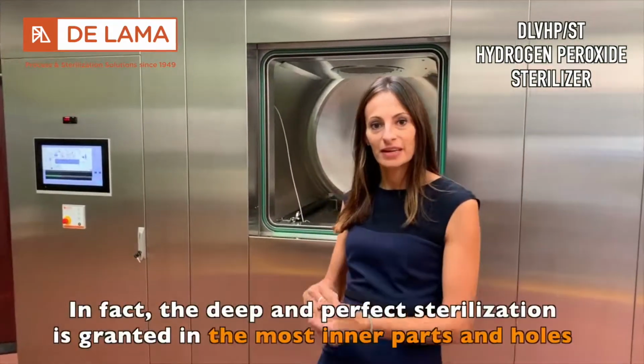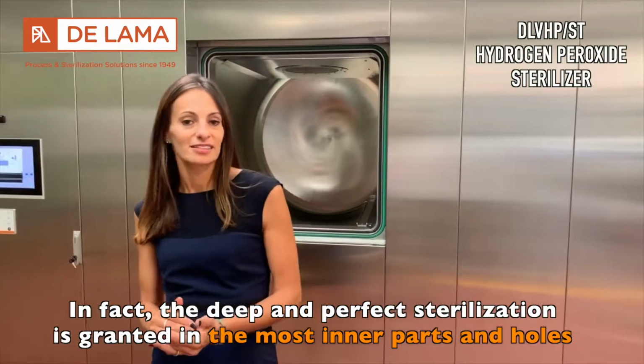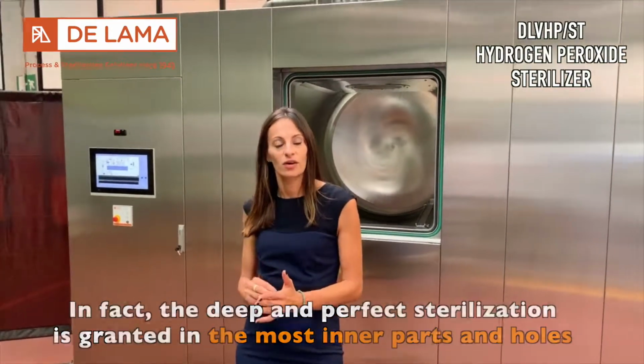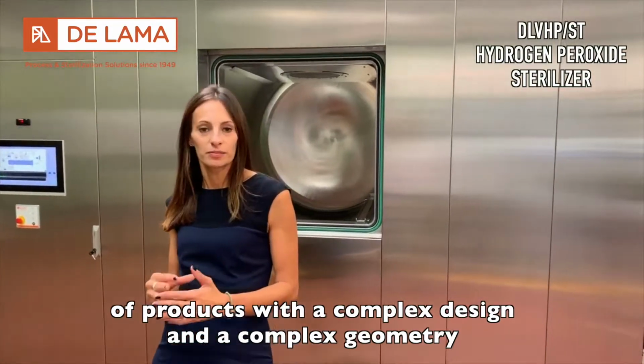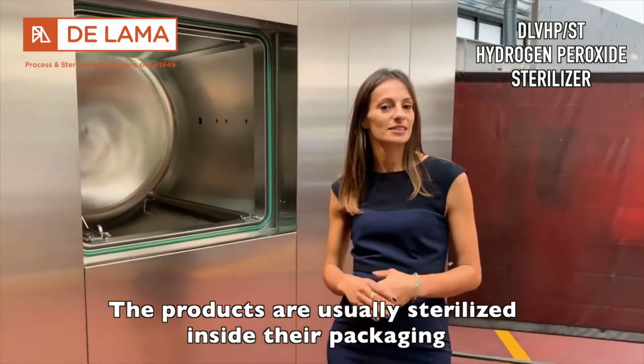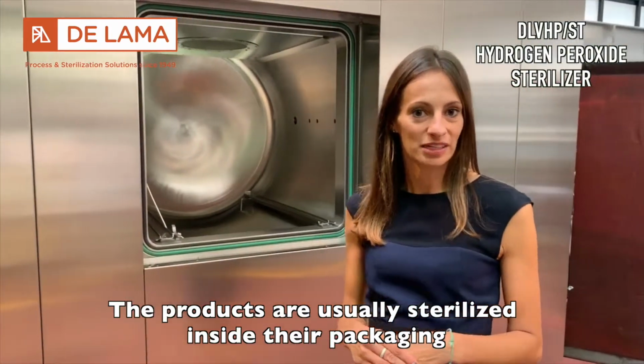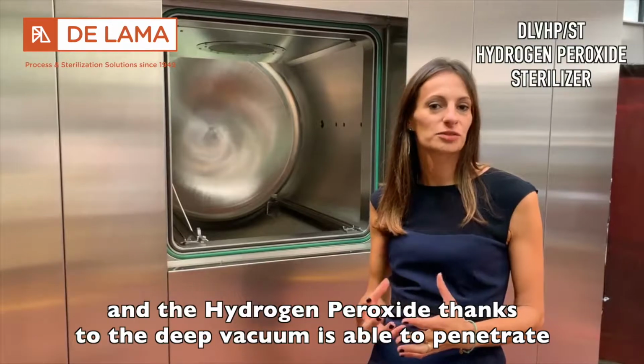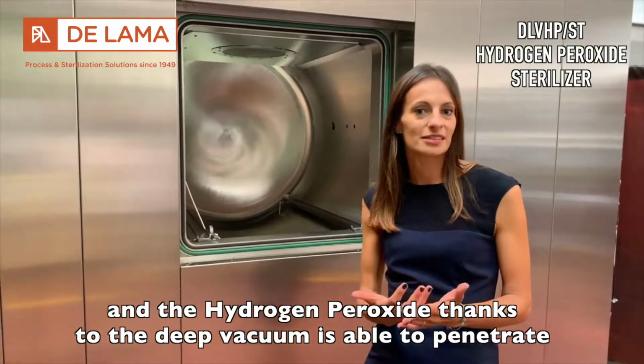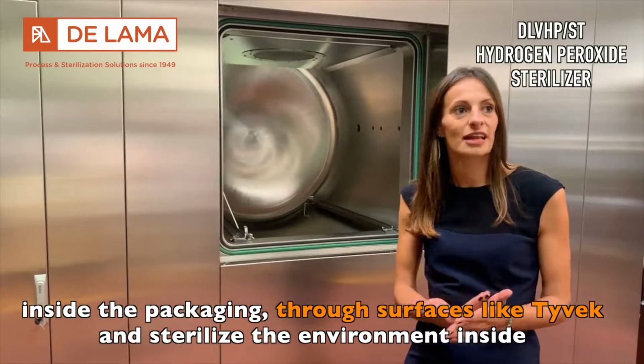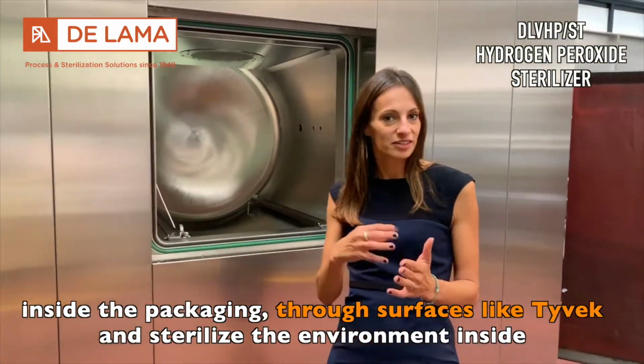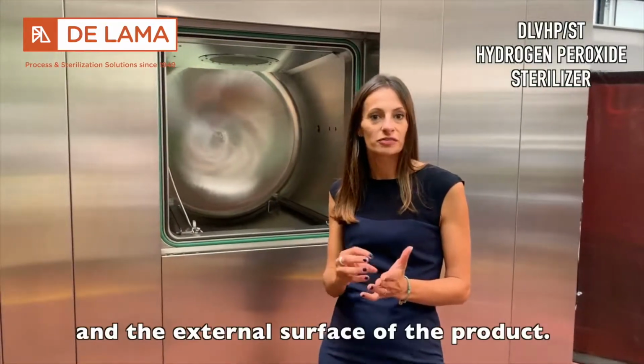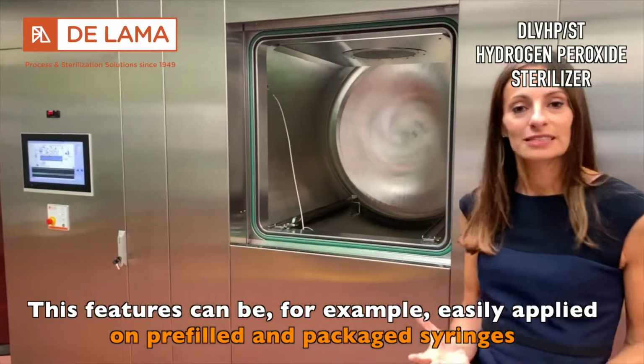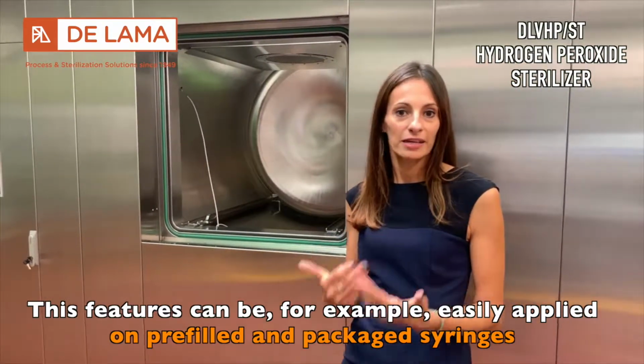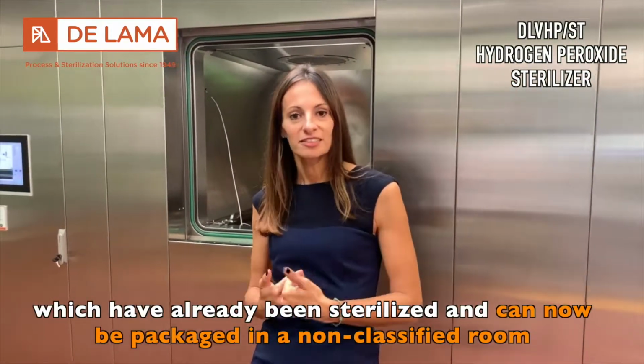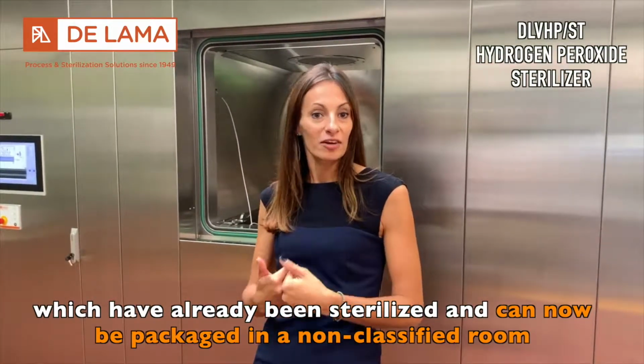In fact, the deep and the perfect sterilization is granted in the most inner parts and holes of a product with a complex design and complex geometry. The products are usually sterilized inside their packaging, and the hydrogen peroxide, thanks to the deep vacuum, is able to penetrate inside the packaging into the surface like Tyvek and sterilize the environment inside and the external surface of the product. This feature can be, for example, easily applied on pre-filled and packaged syringes, which are already sterilized and can be packaged in a non-classified clean room.